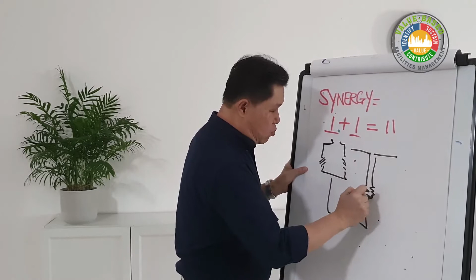Take some time to just do a quick drawing. Okay, last month what I mentioned was the cooling water over here in blue, whereby the risk refers to using a commodity product like chlorine, and if you are not monitoring very closely, the impact to the system can be pitting of the heat exchanger, because chlorine will attack steel, and if there's pitting, then the heat exchanger inside the chiller may have to shut down for repair work. Today I'm going to emphasize this synergy, how another system on top of the chemical water treatment can be used to save on utility costs, for example electricity, and even water.